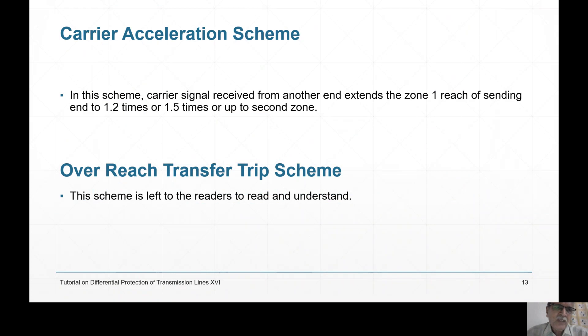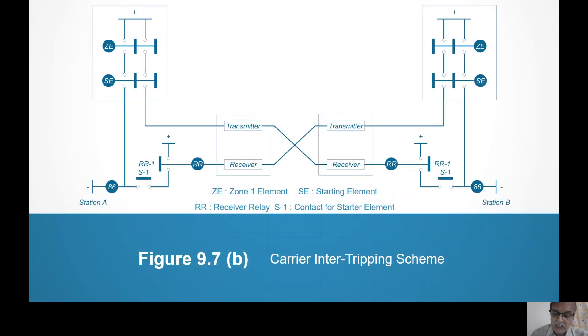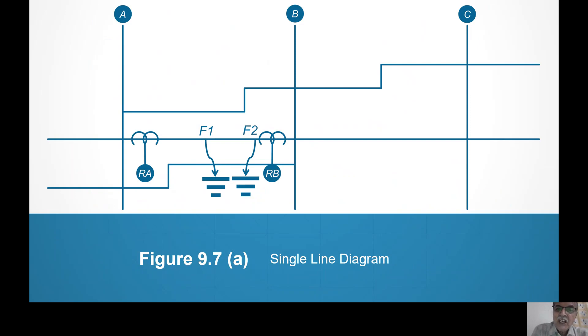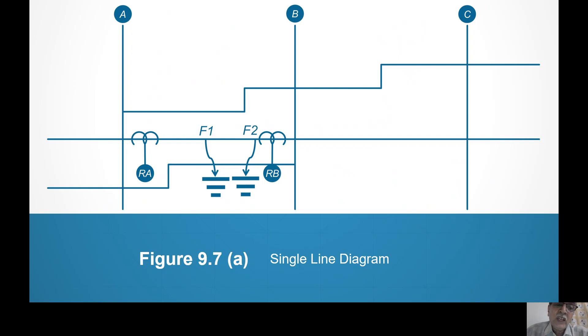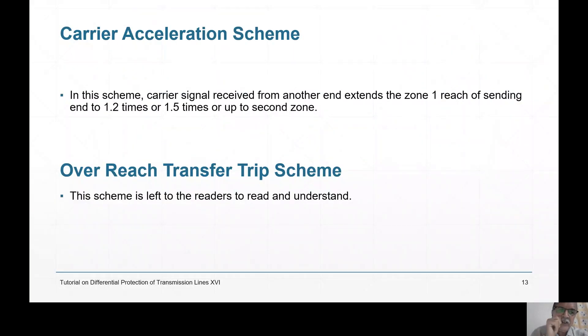Another is the carrier acceleration scheme, which is more or less similar. In the carrier acceleration scheme, if the fault has occurred at F2 and it is in zone 1 of RB, then zone 1 of RB will send a signal to RA to extend its zone 1 to whatever length multiplier is selectable — up to B or beyond B. So zone 1 at A will accelerate; the setting of zone 1 will be multiplied. Carrier acceleration is very commonly used, along with carrier inter-tripping.